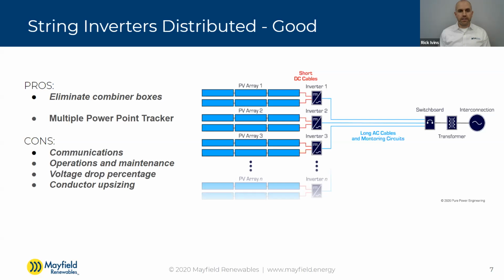Voltage drop percentage: with voltage drop we have two sides, the DC voltage drop and the AC voltage drop. While we may be reducing the DC here, we have the AC at either 480 or 600 volts, which runs longer distances but at a lower voltage than the DC of 1,000 or 1,500 volts. So you're probably going to have to do some more work to keep the overall DC and AC voltage drop effects to a minimum or within an acceptable tolerance. Those lower voltages of 480 and 600 volts mean you just need to upsize those cables a bit more for those long distances.